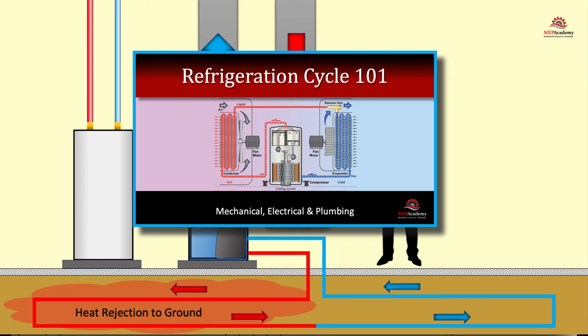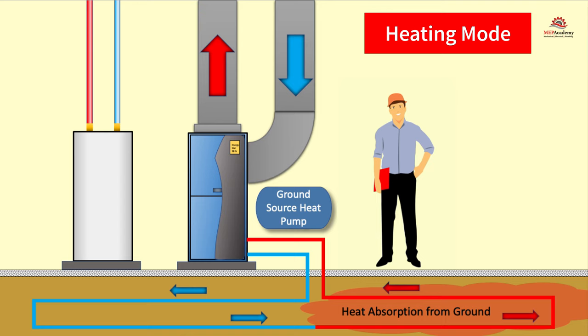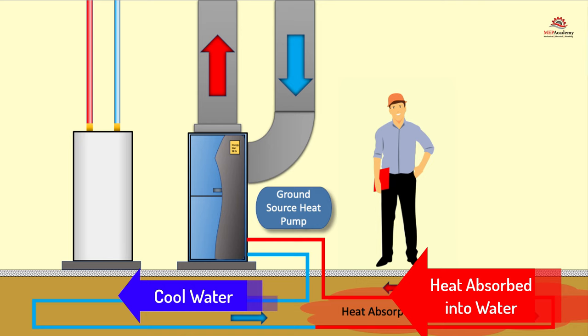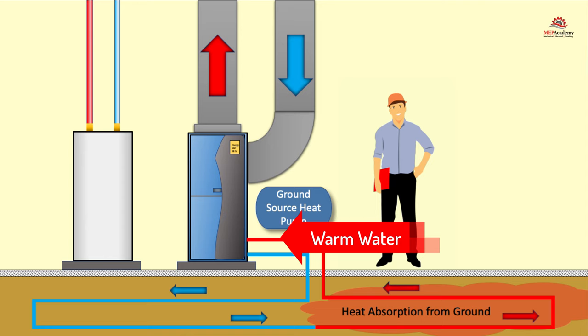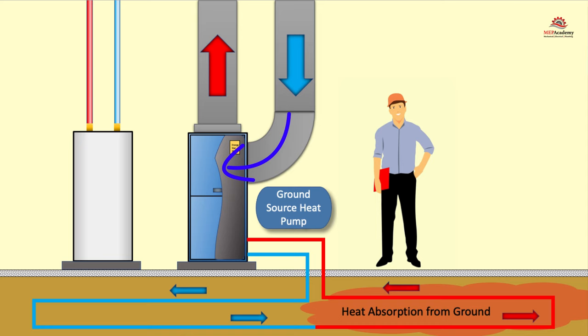In heating mode, the opposite occurs. We will always follow the heat as stated by the second law of thermodynamics. The heat in this case is provided by the ground. The cool water is circulated to the ground where it absorbs heat from the ground. This warm water then circulates into the ground source heat pump where it is absorbed into the refrigerant, causing the liquid refrigerant to boil and turn into a vapor. The hot refrigerant is then circulated to the indoor coil where it comes in contact with the cooler return air from the space. The cool return air absorbs the heat from the hot refrigerant and heats the leaving supply air.